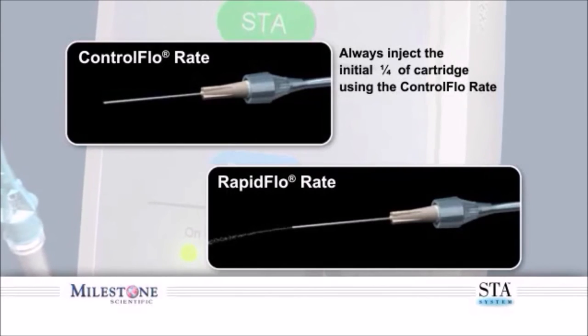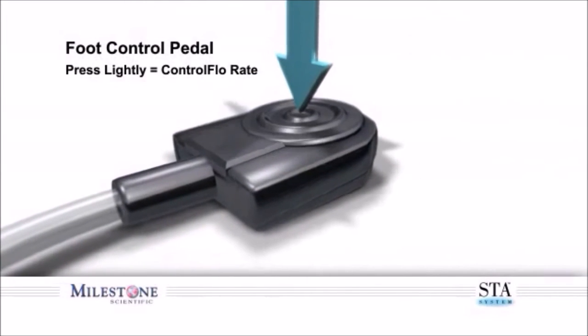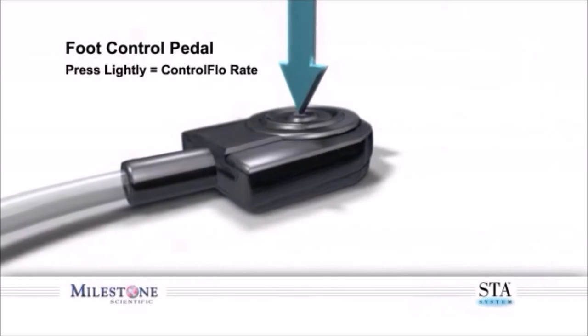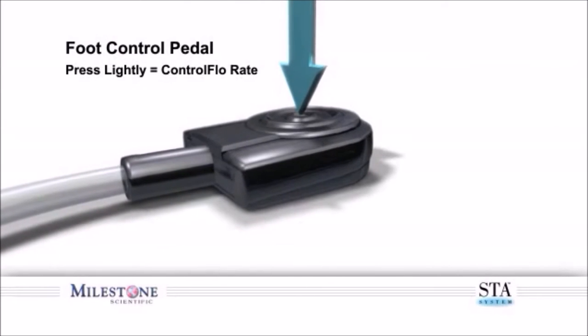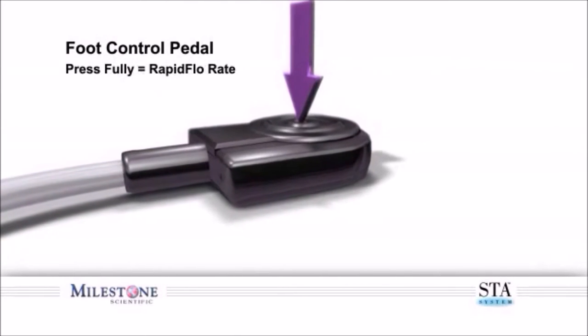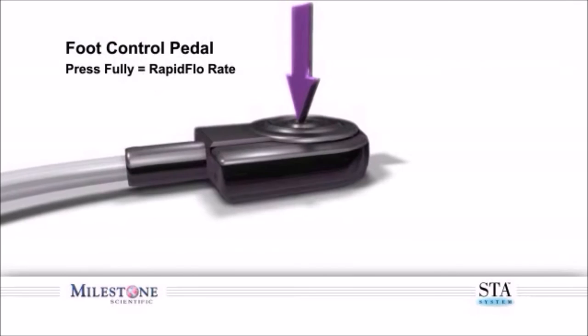Depressing the foot control pedal lightly allows you to enter the controlled flow rate. Fully depressing the foot control allows you to enter the rapid flow rate. There is a corresponding beeping tone to distinguish these two rates that you will hear.